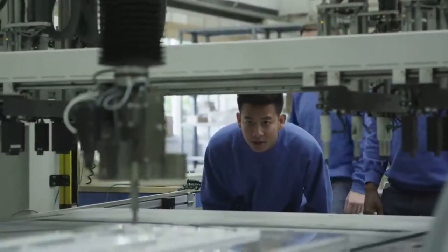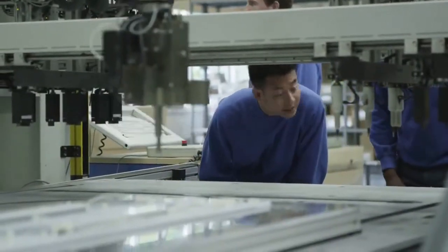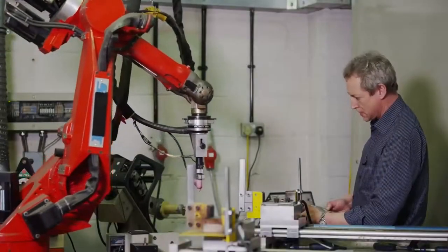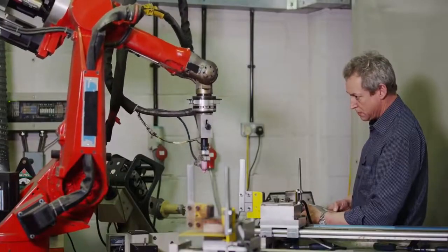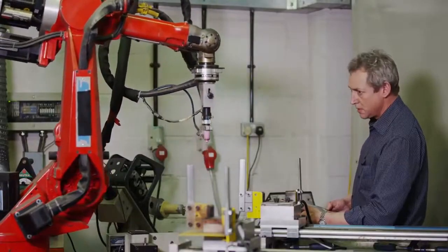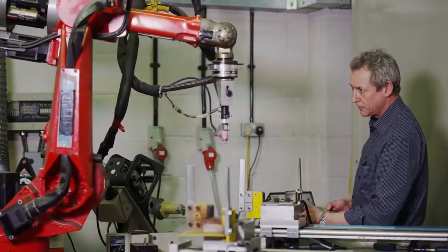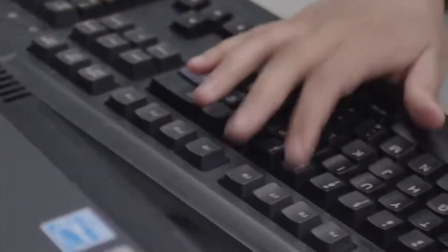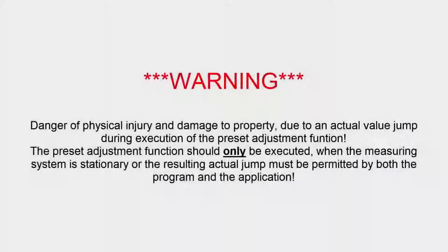In all applications, you will mount the encoder and couple the encoder's shaft to your monitored shaft. Next, you may need to synchronize the physical real-world position of your equipment with the encoder's measuring system. Commonly, this will involve manually jogging the equipment to a known location or measurement, and either zeroing the value from the encoder or defining your own custom value.